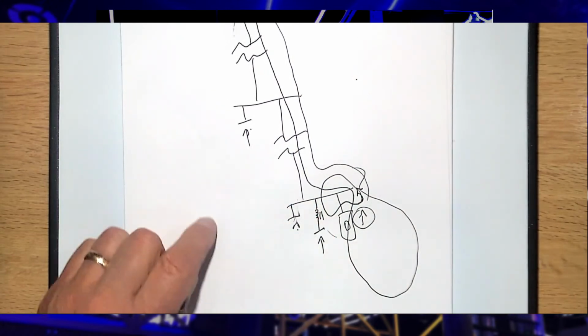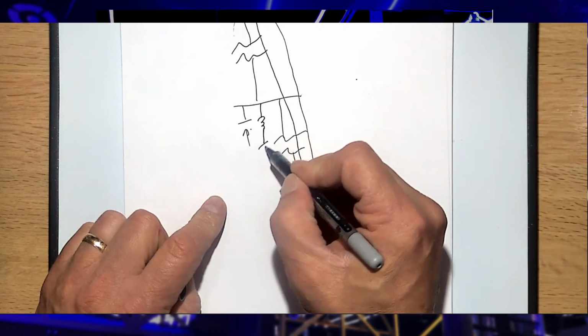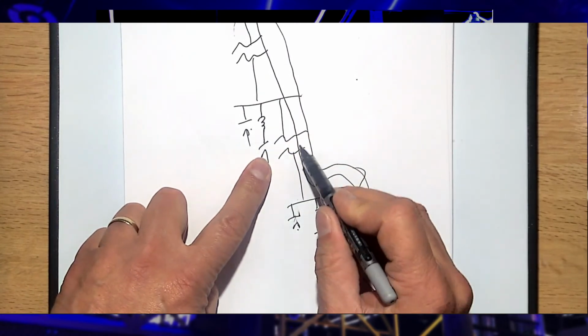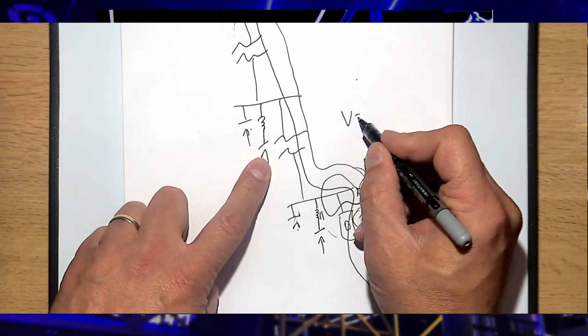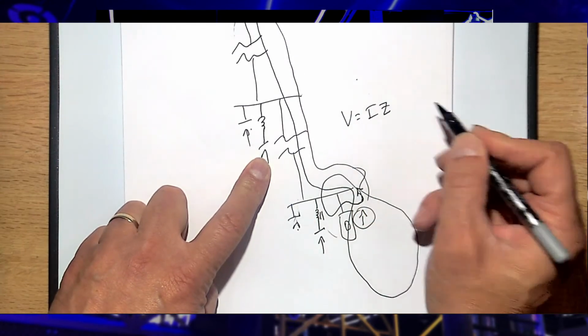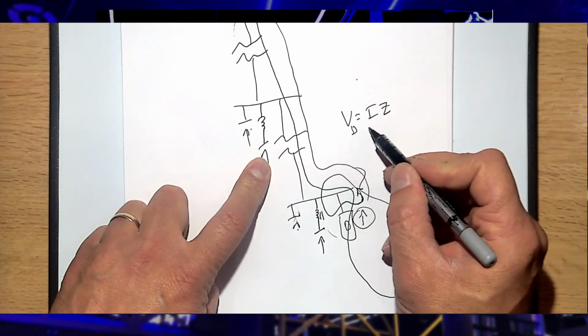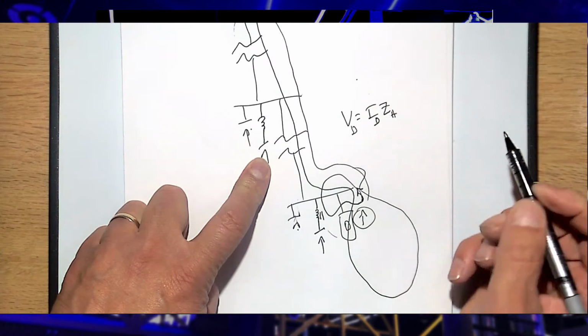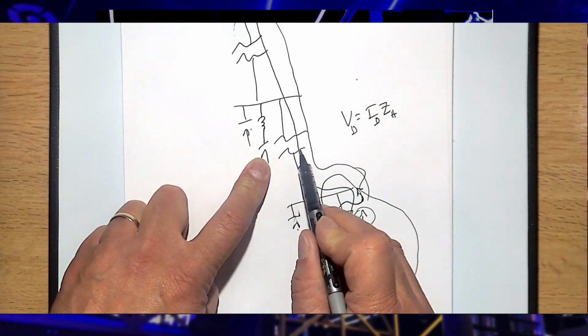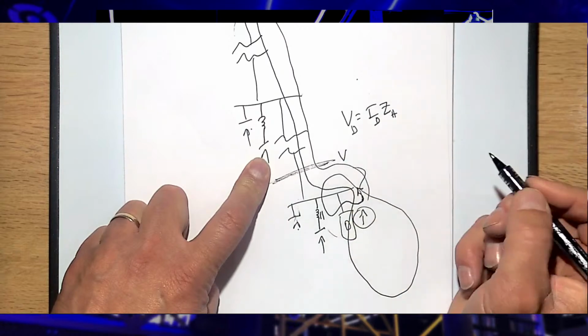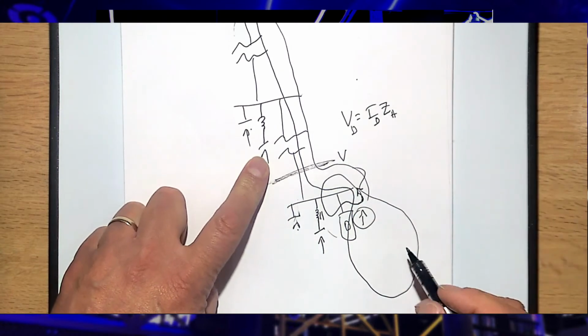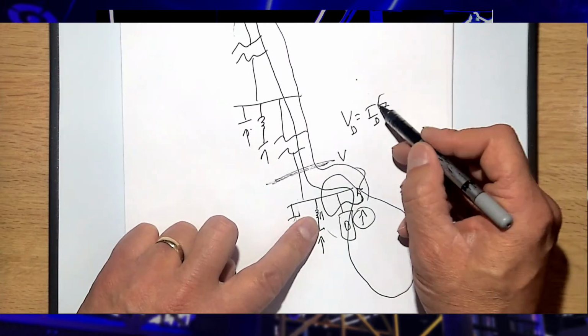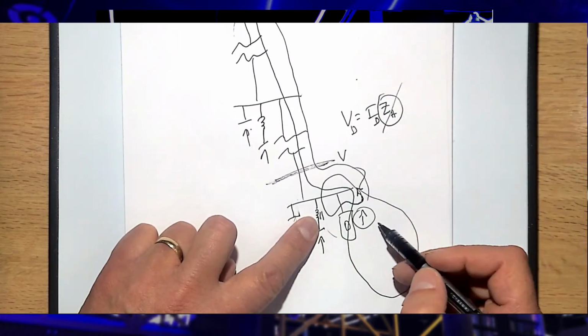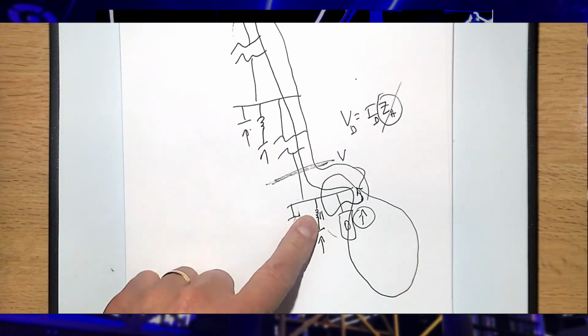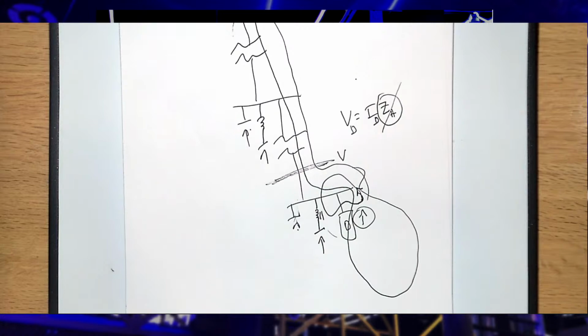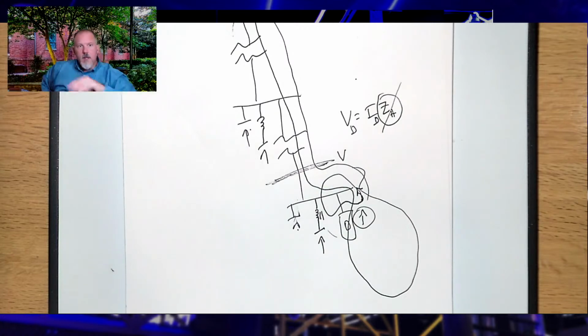So if I don't put a harmonic filter here, I'm pushing harmonics up through a transformer, and here's Ohm's law. Remember all these things we talk about: voltage distortion equals current distortion times harmonic impedance. So if I push my harmonics through here, I'm going to screw up my voltage here. If I put my harmonic filter here, my impedance is basically zero, so I don't get any voltage drop. So the closer you put the harmonic filter to the load, the less voltage distortion you'll have.